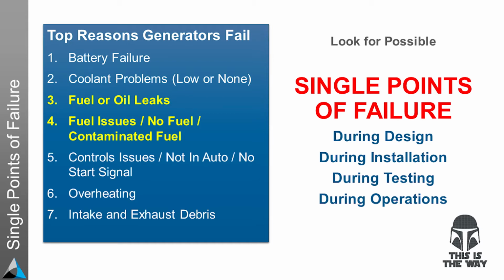One of my jobs as the commissioning provider is looking for single points of failure - in the design phase, construction phase, testing phase, and beyond. Where are those single points of failure potentially living that will make the system not work? If you go through the top reasons why generator and emergency power systems fail, right after batteries it usually has something to do with the fuel system. This is not an unimportant thing, and I'm surprised how often it gets overlooked, because if the fuel systems aren't working, your generator's not going to run for very long.